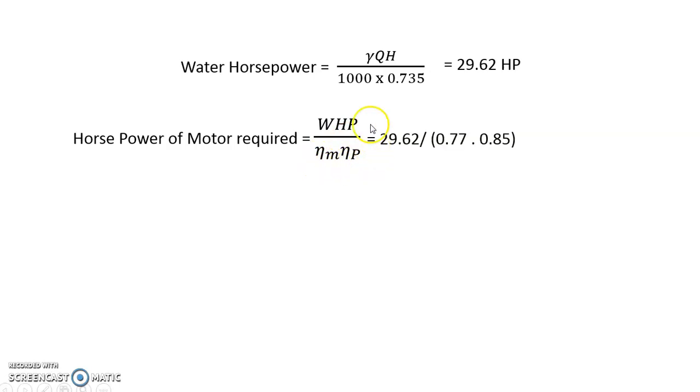So water horsepower calculated is 29.62 divided by 0.77, this is for 77 percent, into 85 percent is written as 0.85 in terms of fractions. So the horsepower of motor required is around 45.26 horsepower, this is the power of motor.